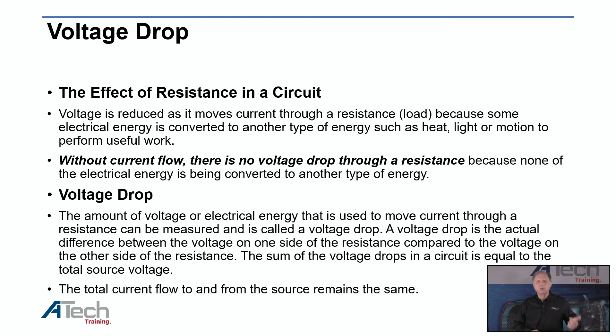If you look across the connection, there should be 0 voltage drop. It should be 0.2 across the wire or cable, 0.3 across a switch, and sometimes you'll see more. If you see more than that, you know the switch is starting to go bad, or you have a bad connection. 0.1 or 100 millivolts on ground. If the value is not listed, use the service information.